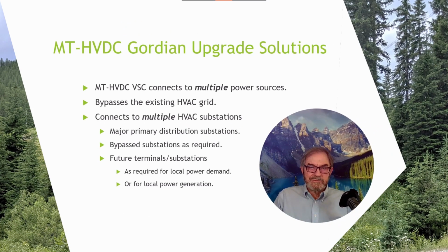We have more options with the multi-terminal upgrades. MT-HVDC connects to multiple power sources, bypasses the existing AC grid, connects to multiple AC substations, including not only major distribution substations, but also bypass substations that require capacity replacement, and new terminal substations, as required for local power demand or for local power generation.